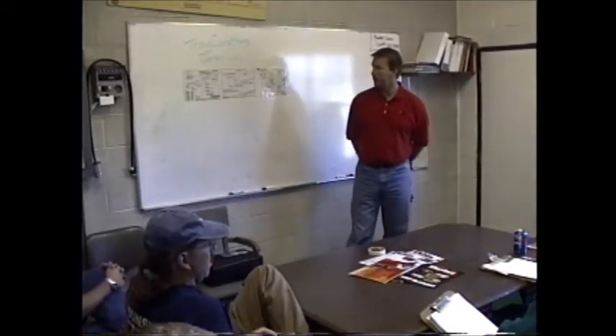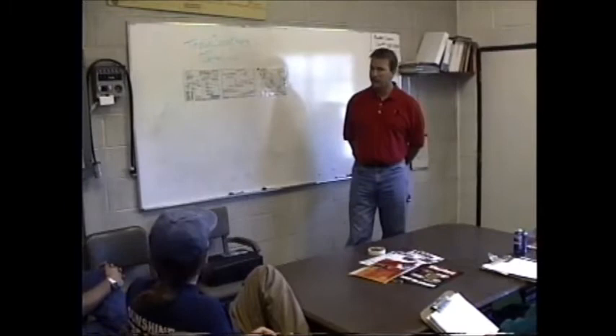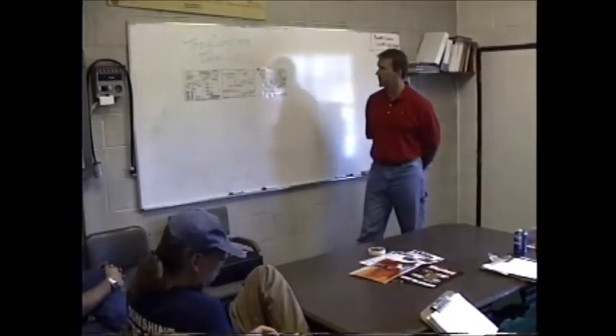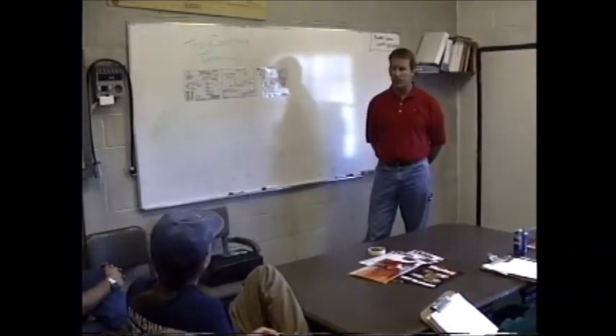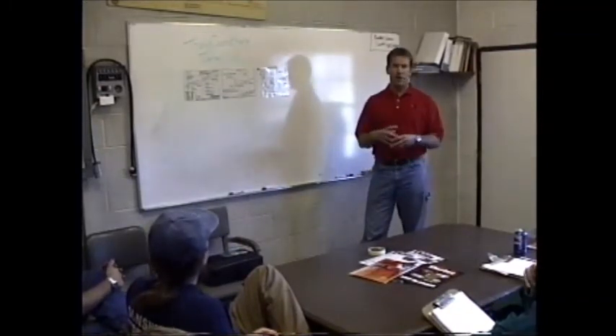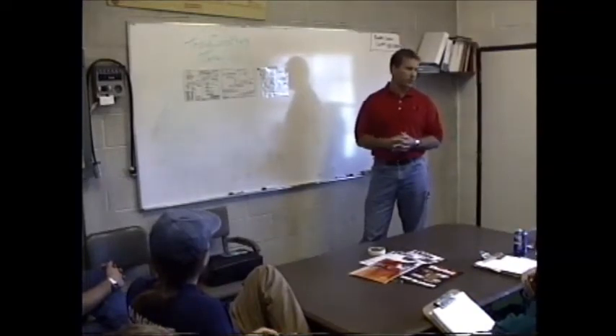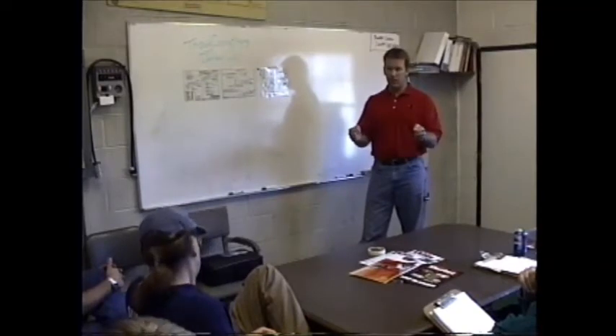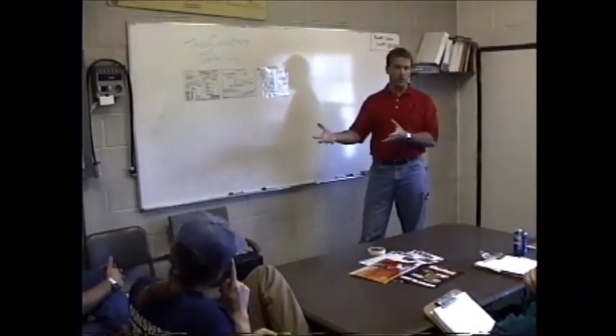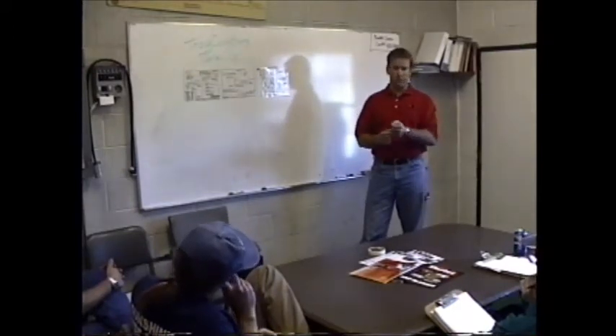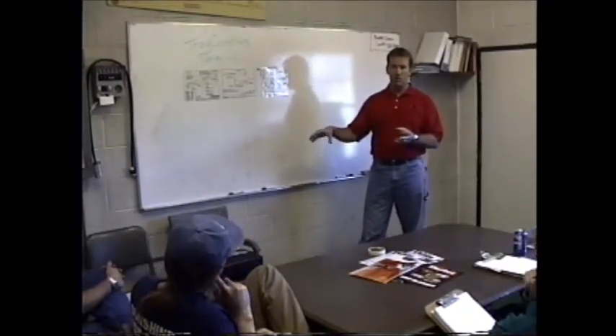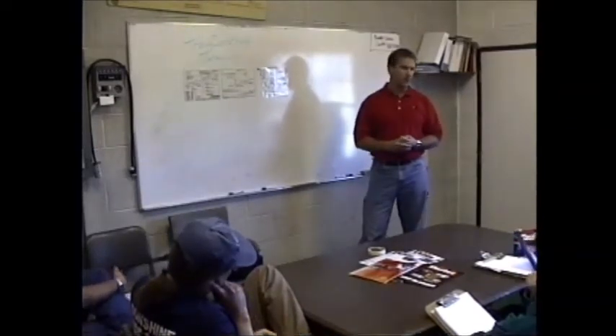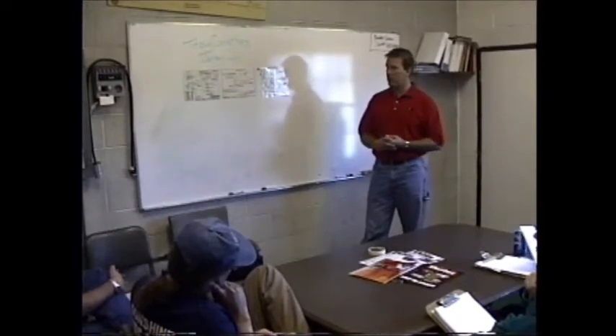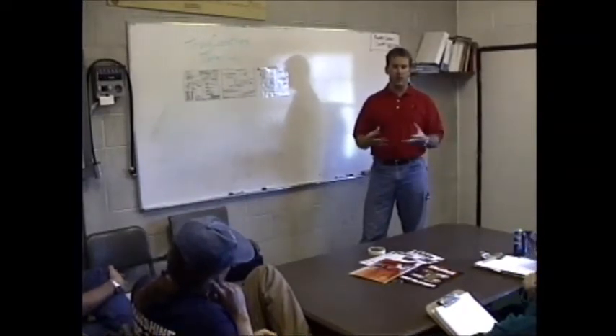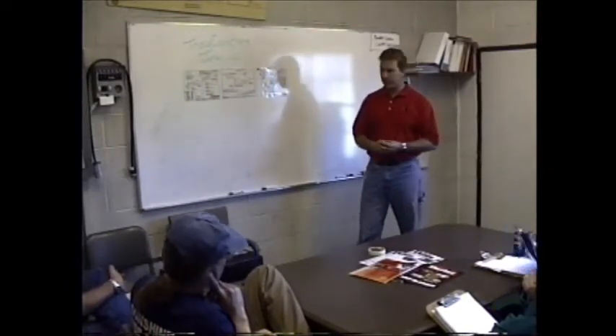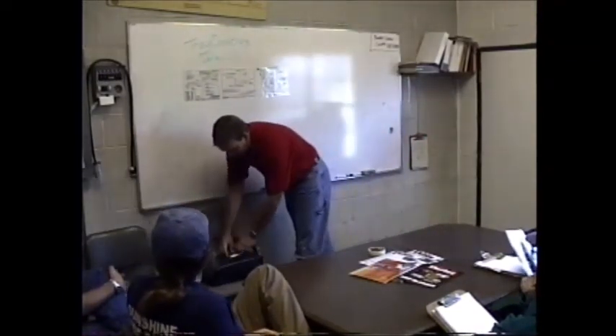Okay. I know this is kind of small print here, but I think we can work through this pretty easily. What I'd like to start to do through the training is at least explain how a basic plumbing schematic works, what components are used in a compressed air foam system, so that when you're actually standing at the pump panel and you're opening a lever, you know exactly what's taking place inside the pump compartment. So when you pull a lever, you know what valve is moving, you know where the water and the foam are mixing in the line, and you know what flipping a toggle switch to turn on the air, where that takes place and how that works. And then I can also explain all the different things that you can do with those different valves and switches.